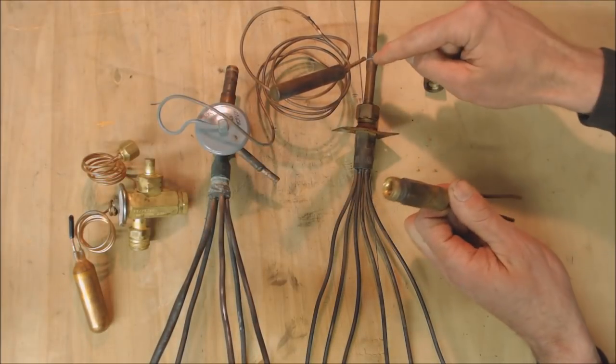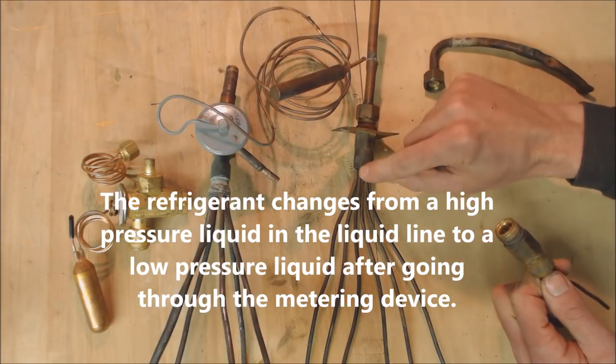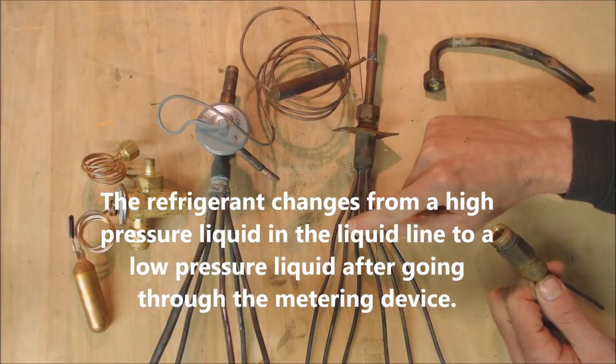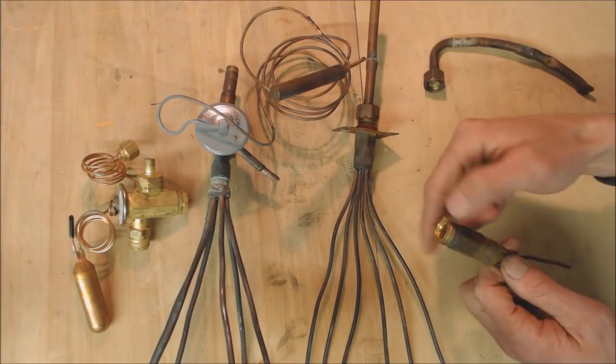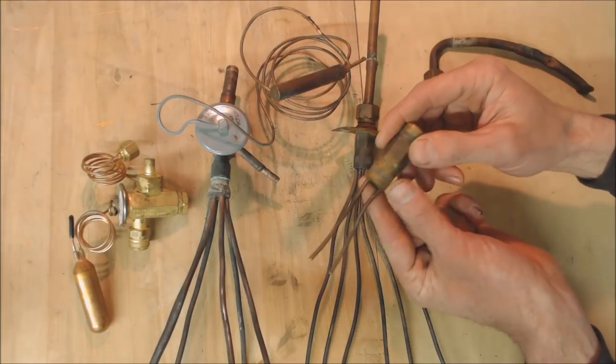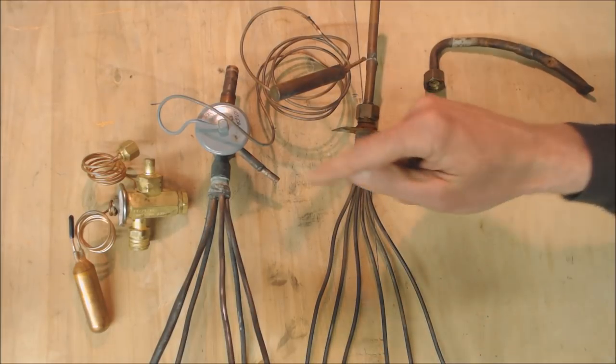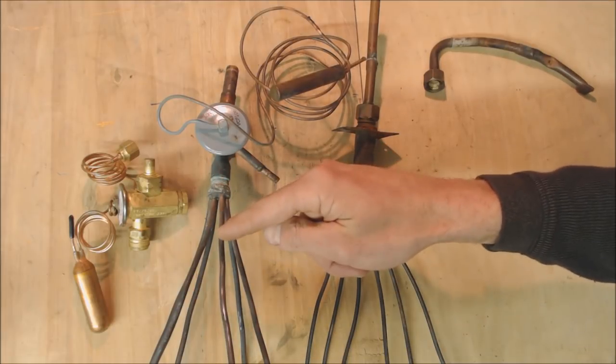After the refrigerant turns from a high pressure, high temperature liquid, it hits the metering device and goes into the distributor tubes that enter the evaporator coil. This one has six distributor tubes and this one has two. Even if you have a TXV, you're still going to need the distributor tubes to go to the evaporator coil.